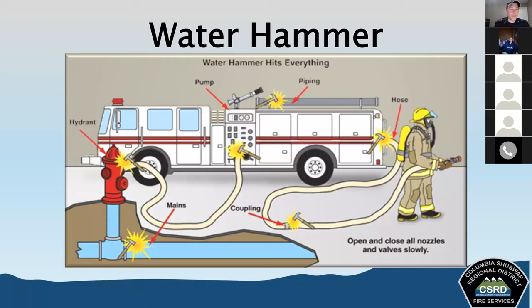Water hammer is basically a surge in pressure caused by a sudden stop in the flow of the stream of water. By having water flowing and then suddenly stopping it, you're taking the kinetic energy of that water that's been flowing through the system, and it's instantaneously converted into increased pressure. Because water doesn't compress, a shock wave goes all the way through that hose and back into the pump.